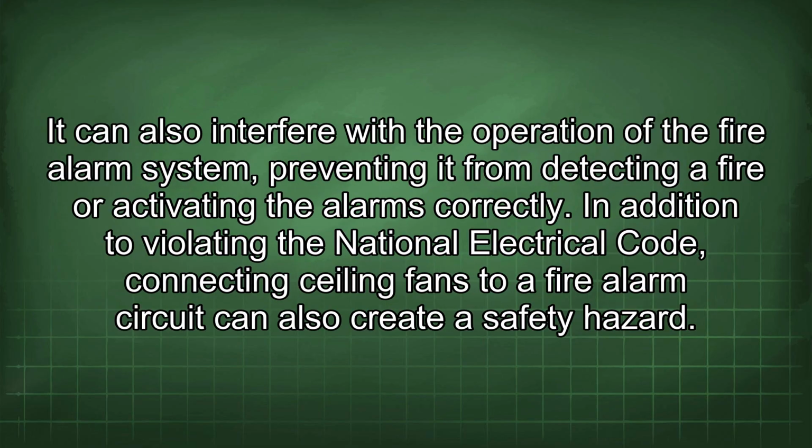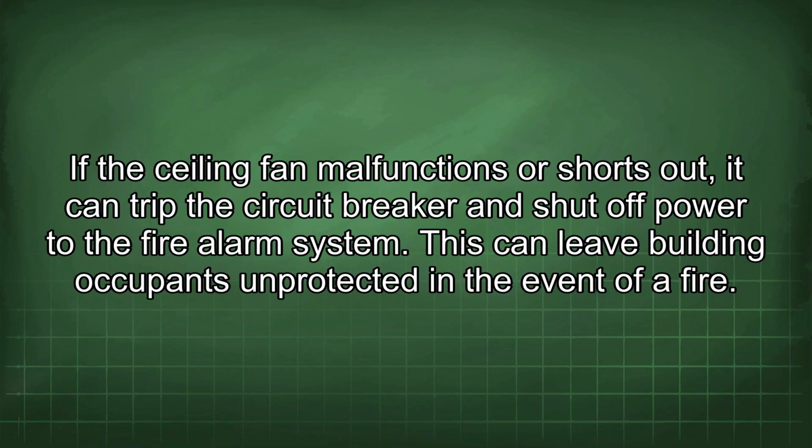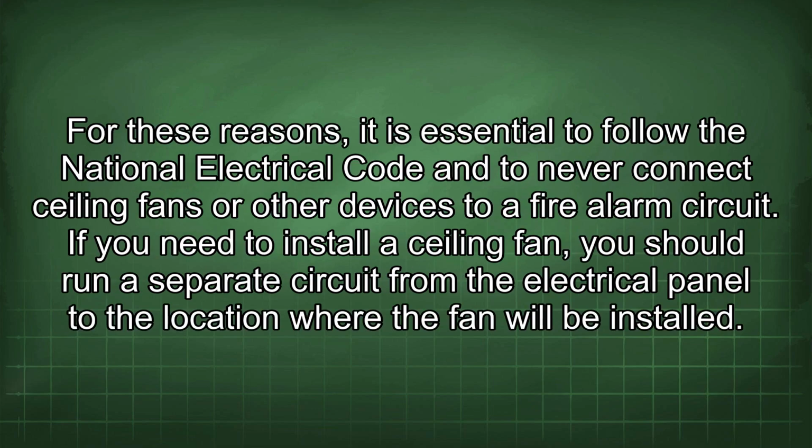It can also interfere with the operation of the fire alarm system, preventing it from detecting a fire or activating the alarms correctly. In addition to violating the National Electrical Code, connecting ceiling fans to a fire alarm circuit can also create a safety hazard. If the ceiling fan malfunctions or shorts out, it can trip the circuit breaker and shut off power to the fire alarm system. This can leave building occupants unprotected in the event of a fire. For these reasons, it is essential to follow the National Electrical Code and to never connect ceiling fans or other devices to a fire alarm circuit.